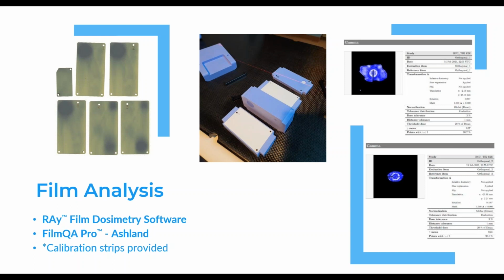For film analysis, there's a couple of softwares we use. We supply the Ray film dosimetry software, and you also purchase the Film QA Pro from Ashland. For film calibration, we do provide the calibration strips as well. We provide 10 calibration strips. And with the Phantom, we actually provide 5 sets of films, so you can do 5 deliveries.